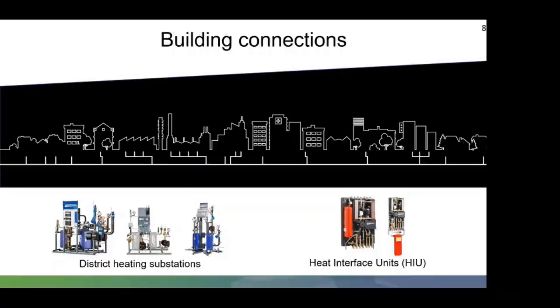Let's just pick that question up now, Mike, by Russell from Steve. What did he say? At 50 degrees C primary flow, how do we ensure domestic hot water temperature? Right. So what tends to happen in Nordic countries is they have a 3-pipe or 5-pipe system. So heating is done via one set of pipes and hot water is done via another. So the hot water flows at a slightly higher temperature to provide you with decent hot water. We do come across this quite often in the UK where people are using heat pumps where the flow is 51, 52. How do you generate hot water? So that's something you've got to bear in mind when you're looking at hot water generation. Is that okay?